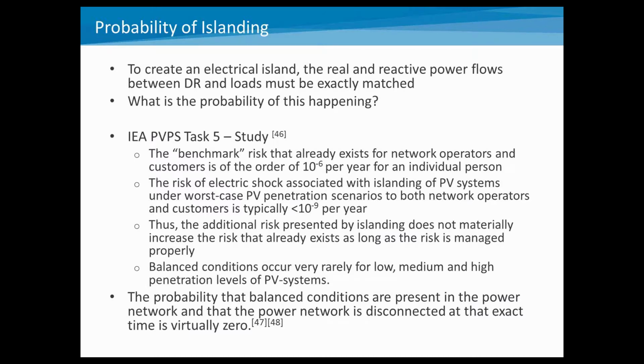So in general, you can read more about it in the reference that's on here, but balance conditions are very rarely occurring, even at low, medium, or high penetration levels, and the probability that these balance conditions are present, that the network can sustain them, and disconnect at that specific time is virtually zero.